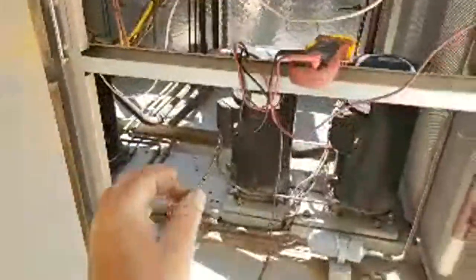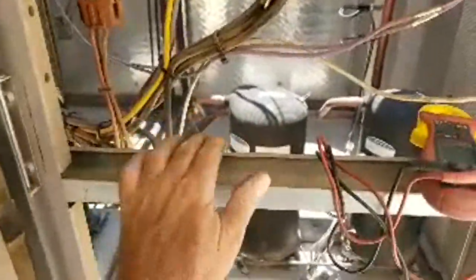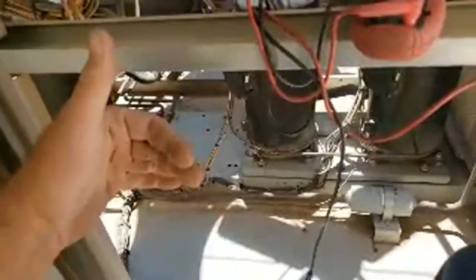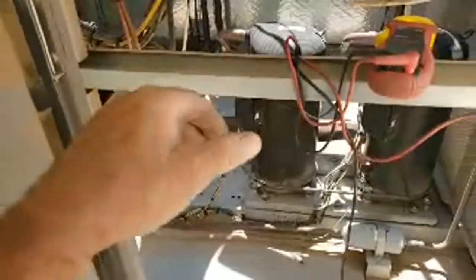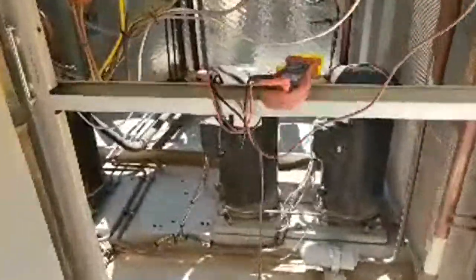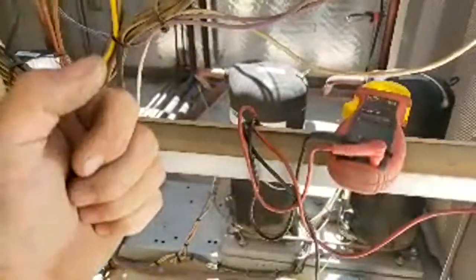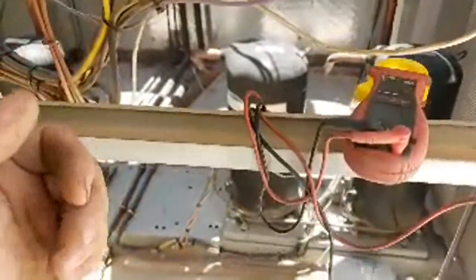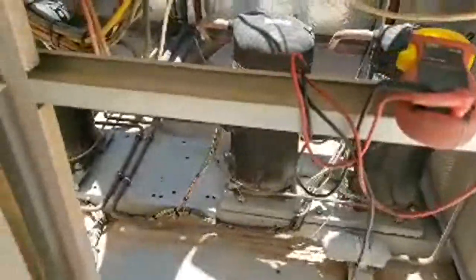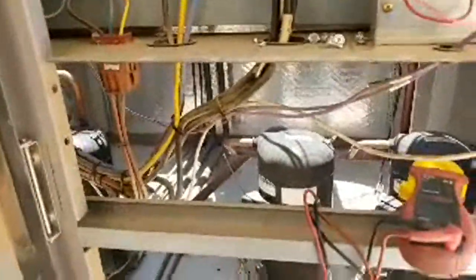Okay, there's a minimum screw which overrides everything, whatever that thing's turned up to. It's a 2 to 10 volt signal. It will be the minimum that the damper can close to. Then the other screw you've got to be careful with is the indoor air quality screw, which has a 2 to 10 volt input coming from the indoor air quality input. If somebody doesn't have the input hooked up, or the input malfunctions, those will drive to fail-safe, which goes to the maximum. I think it says max DCV or something like that. I might be speaking wrong, but something like that on those terminals. And you'll know if you just turn it down, the damper will close.